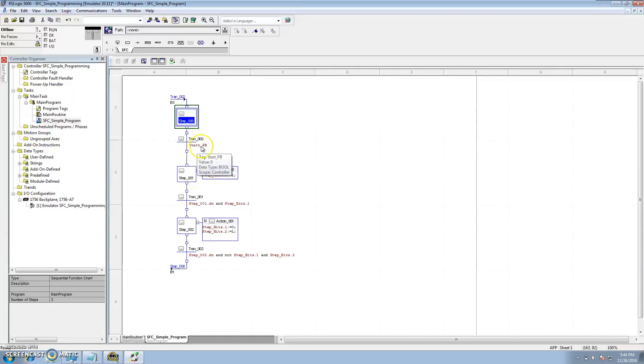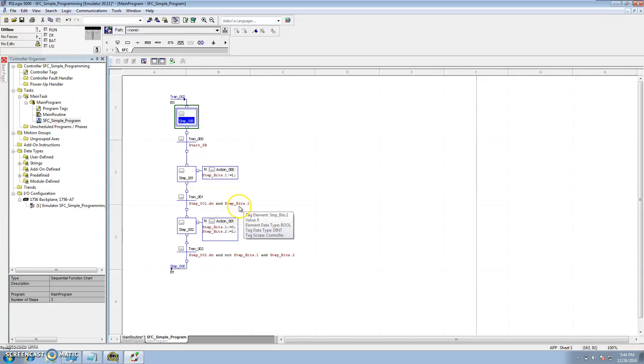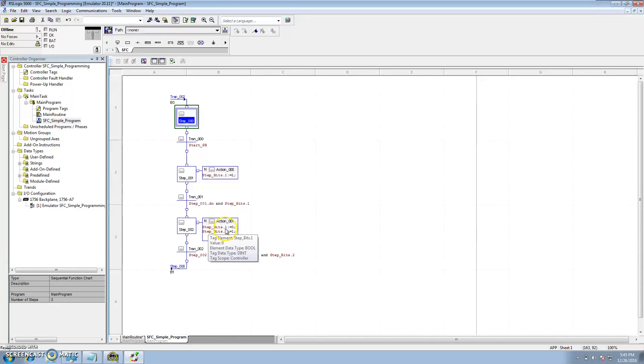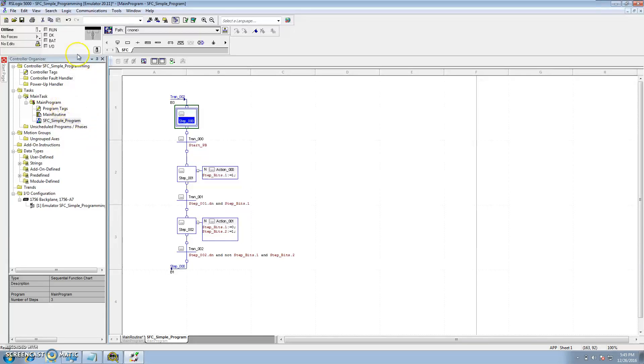So far: step 0 will stay in step 0 if the start button is not on. When the start button is on it goes to step 1, which turns on step_bits.1. Transition 1 checks if step 001 is done and step_bits.1 is on, then goes to step 2. Step 2 cuts off step_bits.1 and turns on step_bits.2. Transition 2 checks step 002 done, bit 1 off, bit 2 on, then loops back. If the start button stays on it keeps cycling.